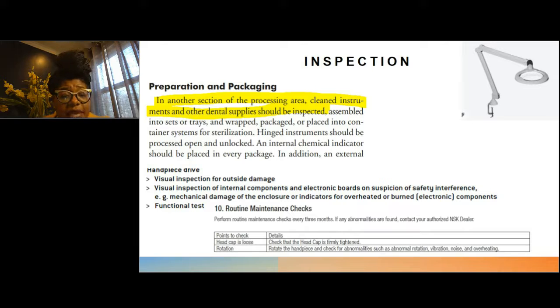Visual inspection for damage. This excerpt from the handpiece IFU says visual inspection of internal components and electrical boards, and a function test, where the handpiece is being run to see if it is functioning properly. If there are issues identified at inspection, then this handpiece cannot go back out to be utilized on a patient. A preventative maintenance plan would need to be developed where those handpieces get sent out and repaired, so that after being repaired they can go back out into circulation.